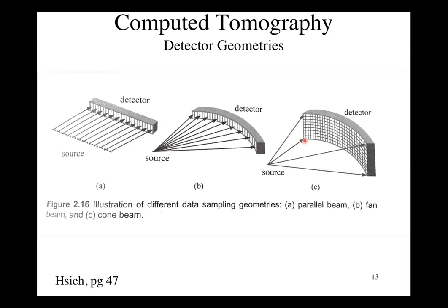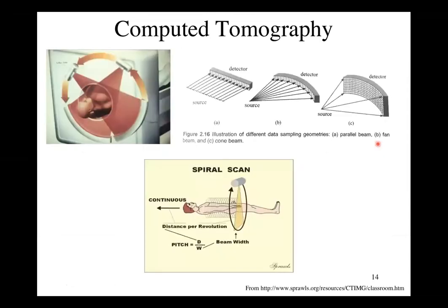Modern CT scanners actually have this arc around the circle, and they have many detectors in the Z direction, along the cylinder as well. Some modern scanners have 320 in this direction, some have 256, some have 64, but it has made a huge difference in the time needed to acquire all the data required to make a CT picture. A ray from the source can be matched to every element in the detector, and so it's just a flash, and I have a two-dimensional picture of the projection of X-rays through that object. So that's the evolution of the detector geometries.